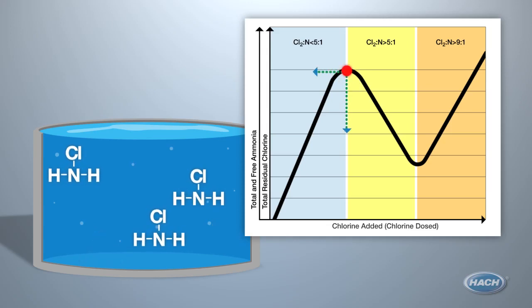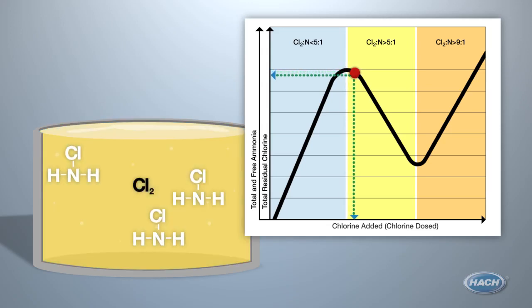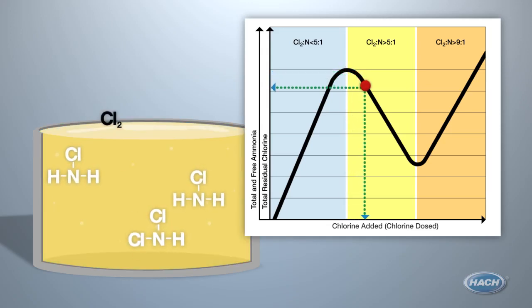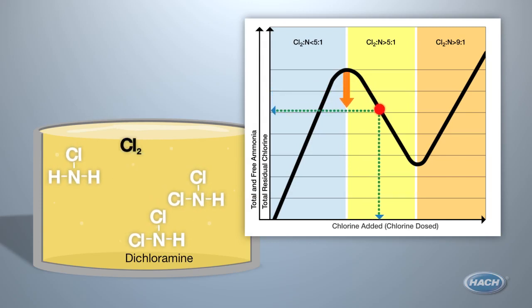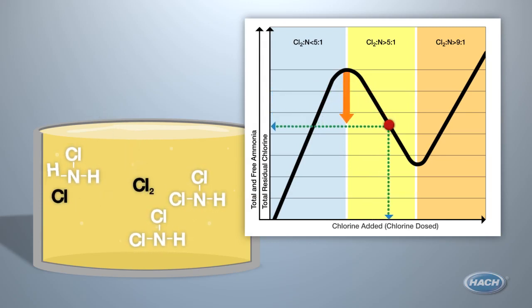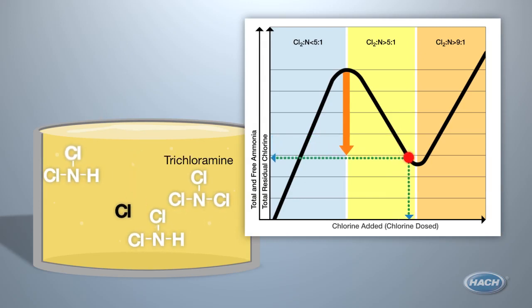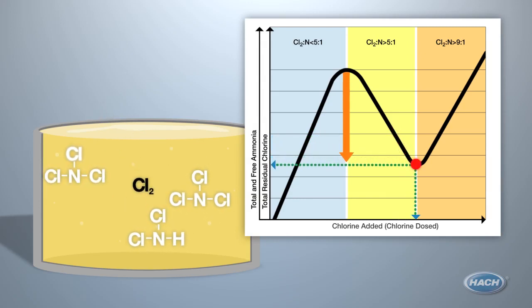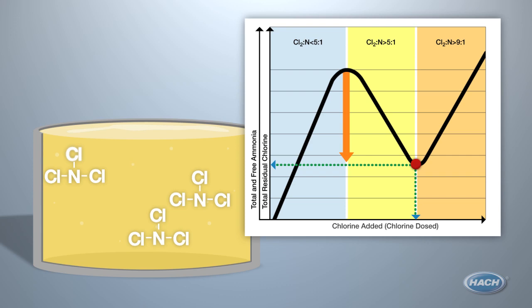If you continue to dose chlorine past this state, you begin to experience di- and finally tri-chloramination. These states are not ideal. It causes your chlorine residual to drop radically, although you are adding more chlorine. You will experience taste and odor issues when you are in this zone, and your disinfecting power is drastically cut.